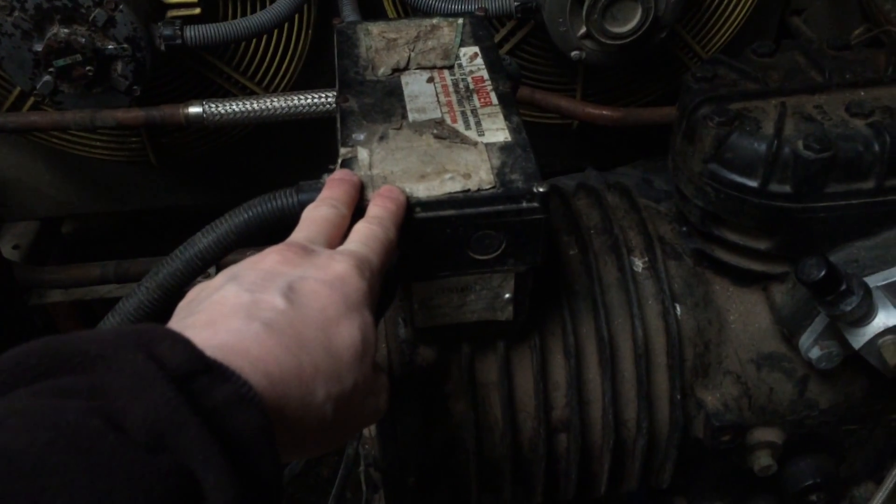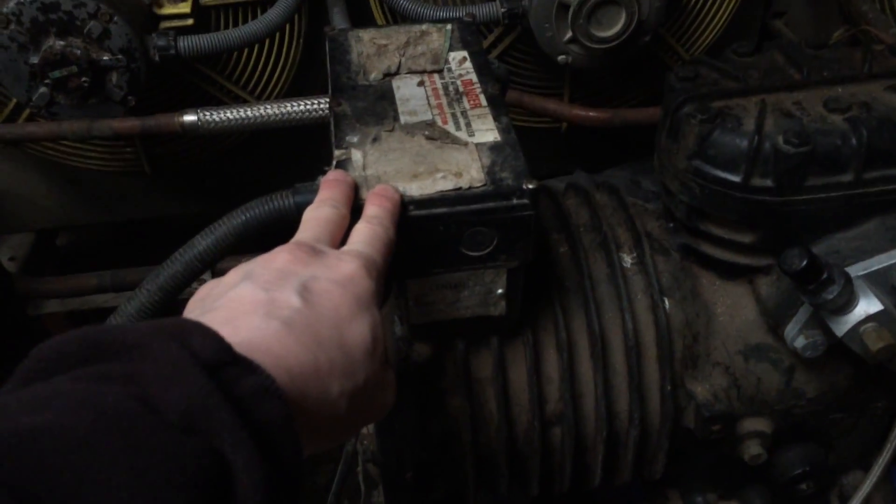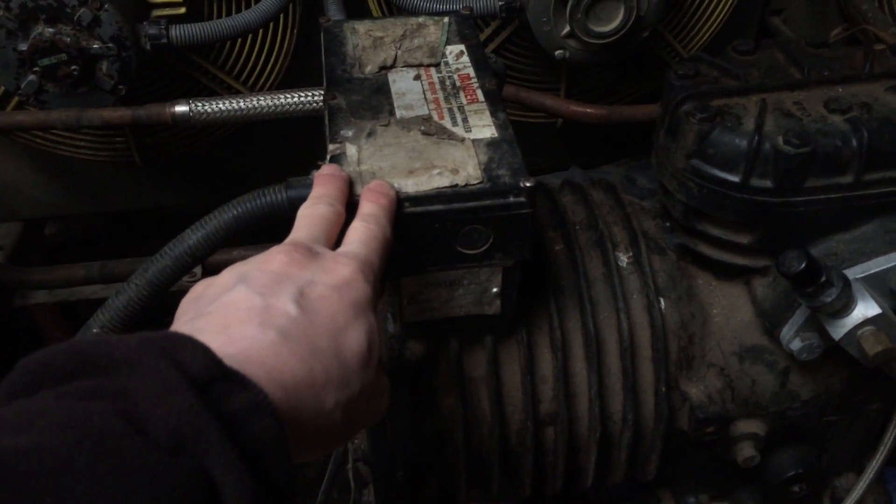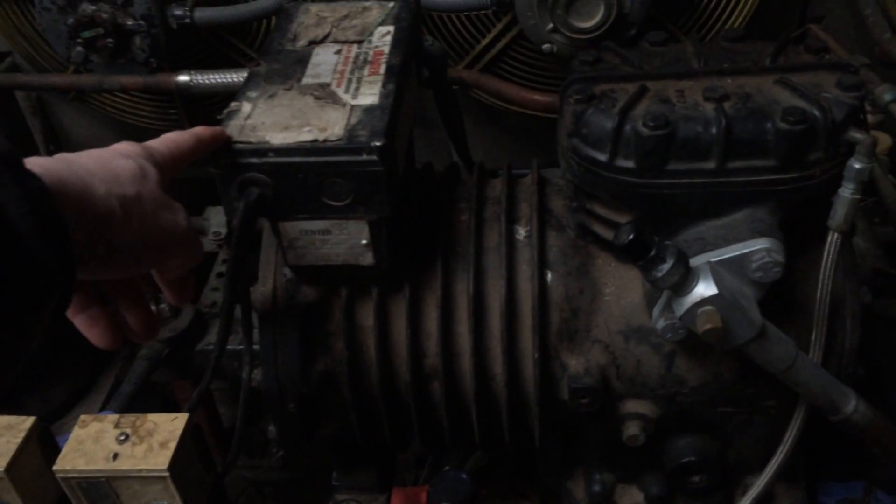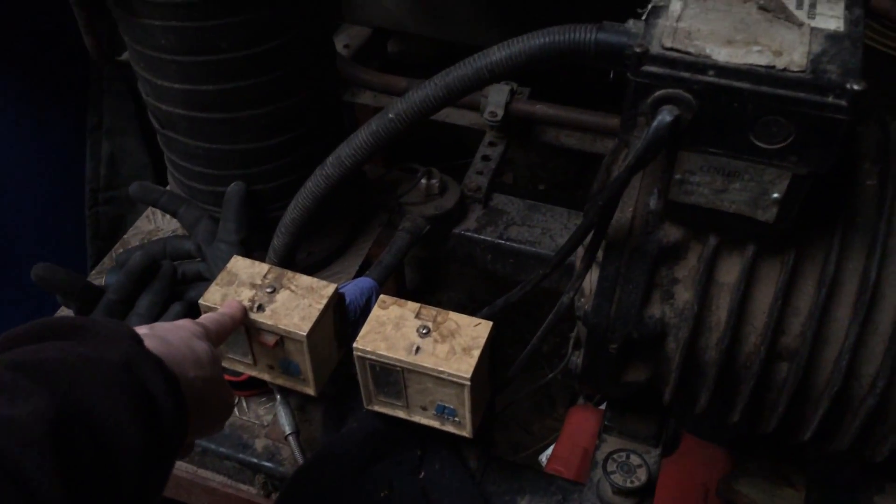When they turn it on it runs for a minute or so and then trips out and you think that'd be a classic symptom of a gas leak or something like that. We've got a manual reset low pressure switch so that's unlikely.